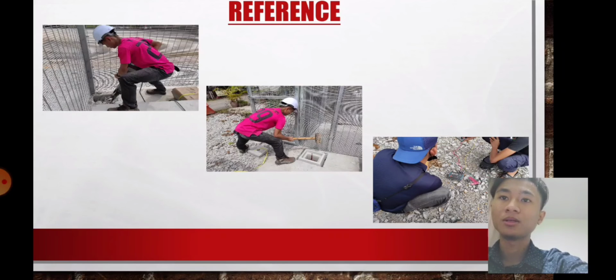Then, cut the wall of the chamber hole using a drill with flat eye until the hole becomes flat and neat. Thus, start knocking the copper rod into the chamber hole by using the big hammer until the copper rod is planted fully, and repeat knocking the copper rod by connecting the copper rods with the connector kit at the same hole, at least 3 pieces of copper rod.